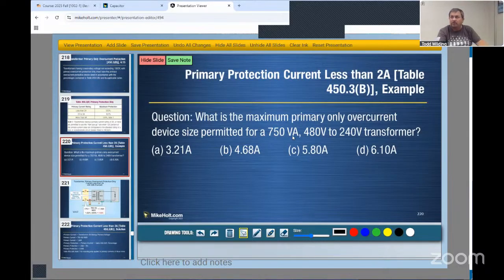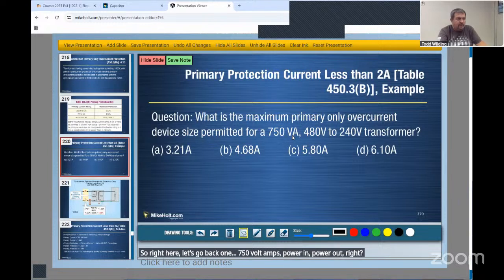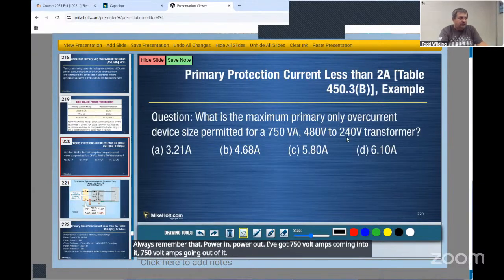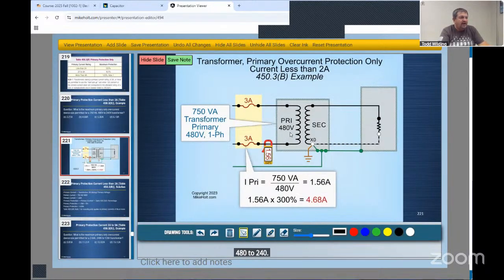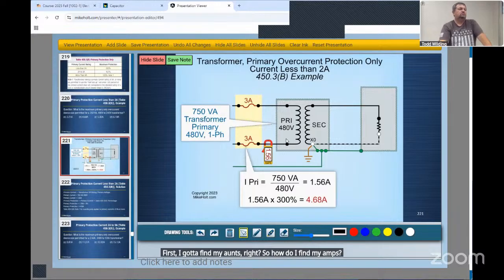750 volt-amps: power in, power out, right? Always remember that, power in, power out. I've got 750 volt-amps coming into it, 750 volt-amps going out of it. 480 to 240: 480 right here, 240 right here. So first I have to find my amps. How do I find my amps? I take the 750 volt-amps and divide by my volts, and I get my amps. Primary current: 750 divided by 480 gives 1.56 amps.